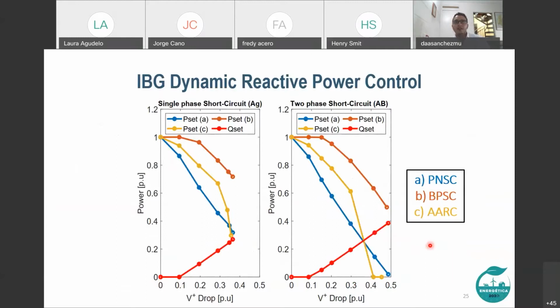So here we present the active and reactive power set points as a function of the positive sequence voltage drop and the inverter control strategy. Here we have the 3 control strategies we checked in the last slides. So here we have the voltage drop start to rise, and then the reactive power set point starts to increase, and of course the active power set point has to decrease. Also, we see that the best control strategy to maintain power injection is the balanced positive sequence control.